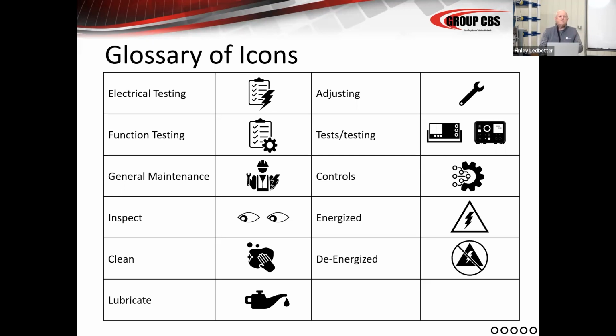Okay, so I've done this. Some of y'all have seen this before, but if you take and you press your hands together really hard, this is the moving contact. This is the stationary contact in a vacuum breaker or an air breaker, whatever kind of breaker you've got. And you push them together, the circuit is closed. So the circuit is energized and possibly it's passing power through the breaker. And then when you do this, it opens and breaks the contact, and then current stops flowing. Potential is no longer applied across the contacts. Essentially on, off, on, off. Pretty simple, right? Just like a valve.